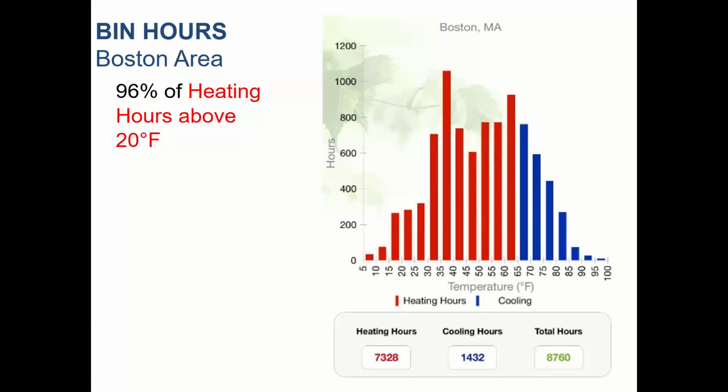And if you didn't know it, every single heat pump from every single manufacturer that gets AHRI listed, which is all of them, is tested at 47 degrees and 17 degrees outside. They've already tested it at 17 degrees. It can be run at 17 degrees. Anyone who tells you heat pumps have to be turned off at 35 degrees, I don't know where that number comes from. It's a total misconception. It was never true to begin with. Anybody who says that doesn't know what they're talking about. Every single heat pump from every single manufacturer is allowed to be run at 17 degrees or lower.